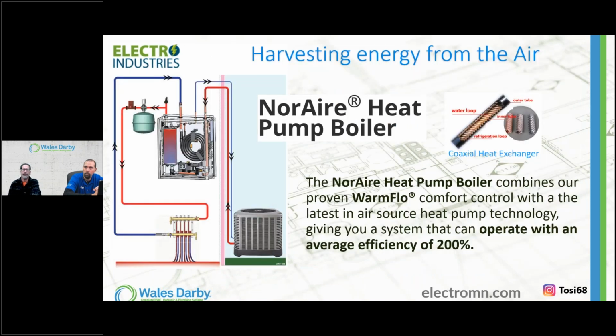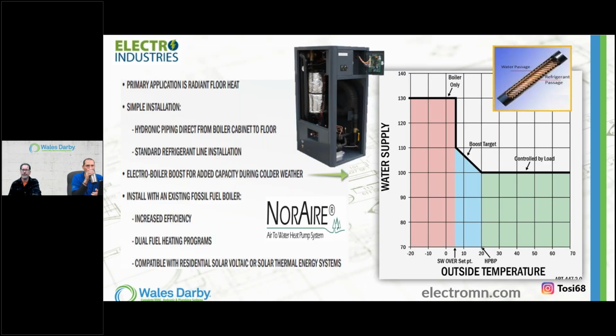So here's a picture of what you can expect. Again, low temperature. If you need high temperature, turn on the boiler, right? Coaxial heat exchanger. One side of that inner tube is refrigerant, the other side is the water. And there's our heat exchange, upwards of 200% efficient.